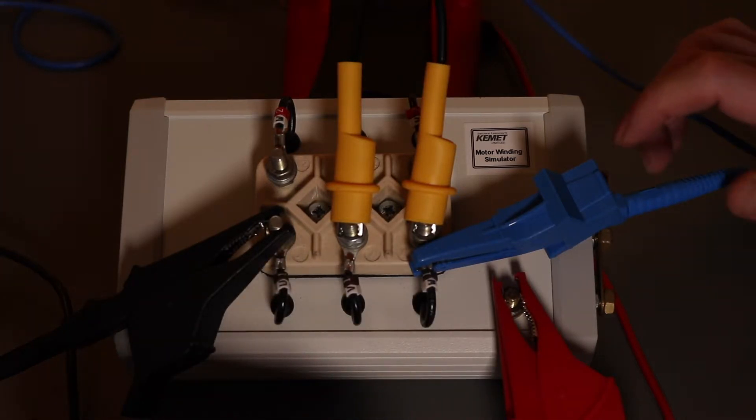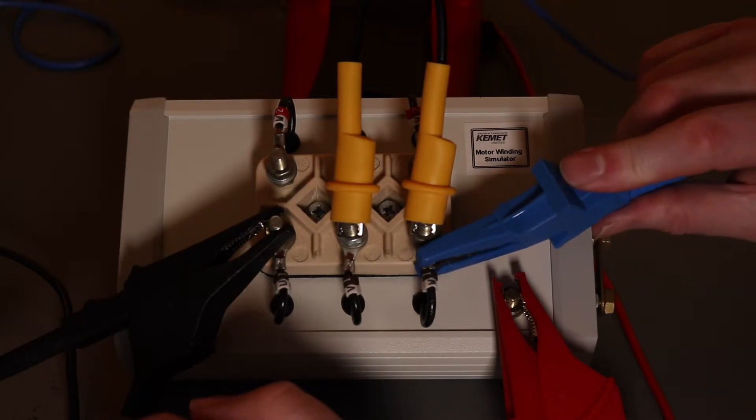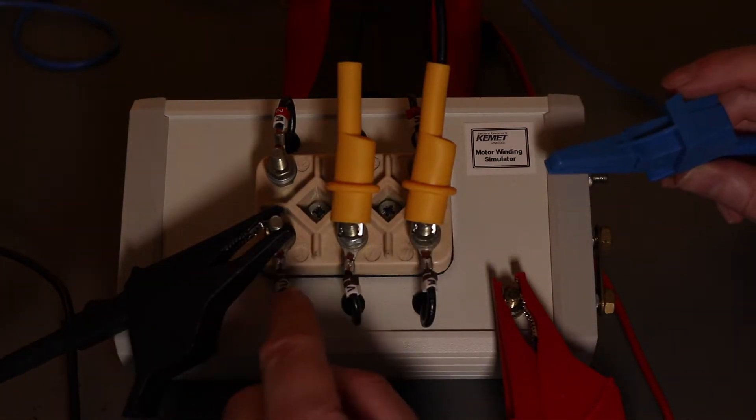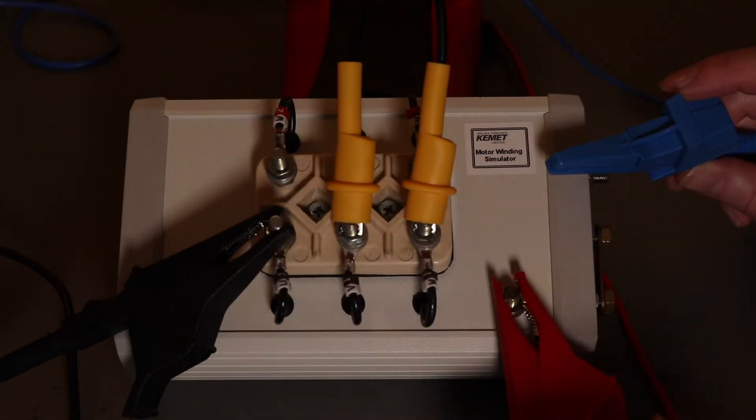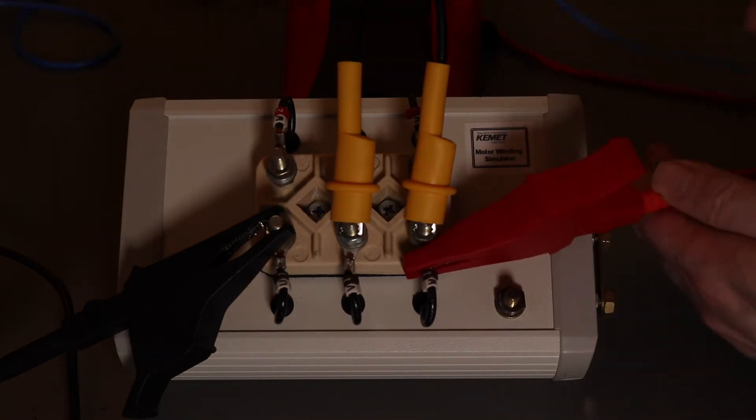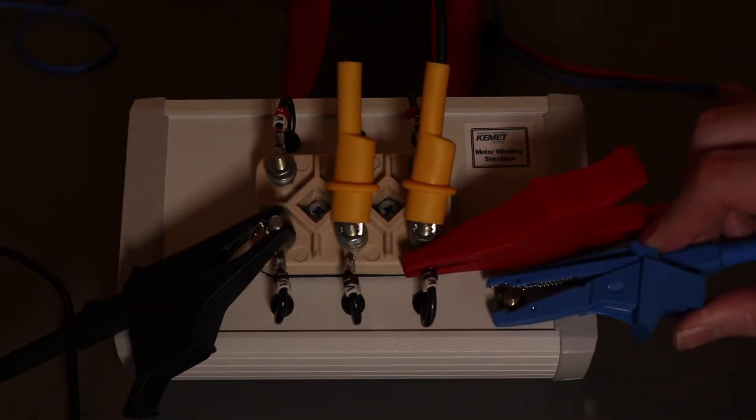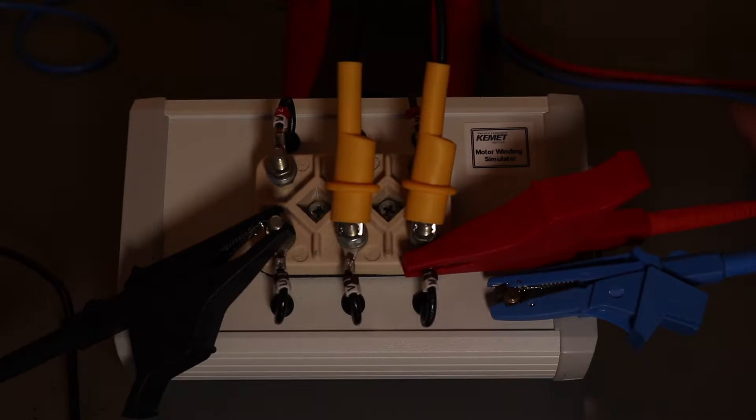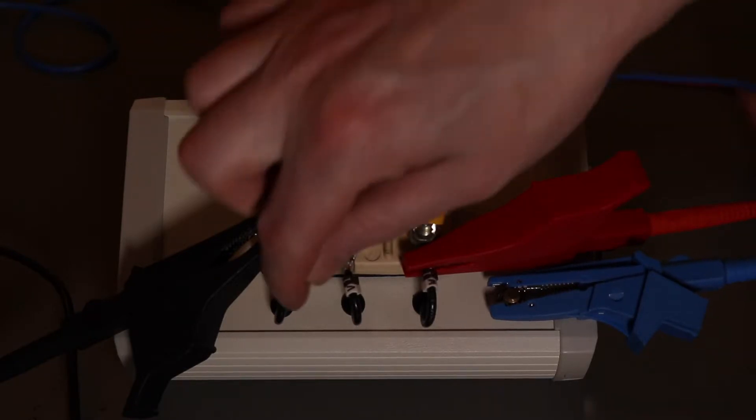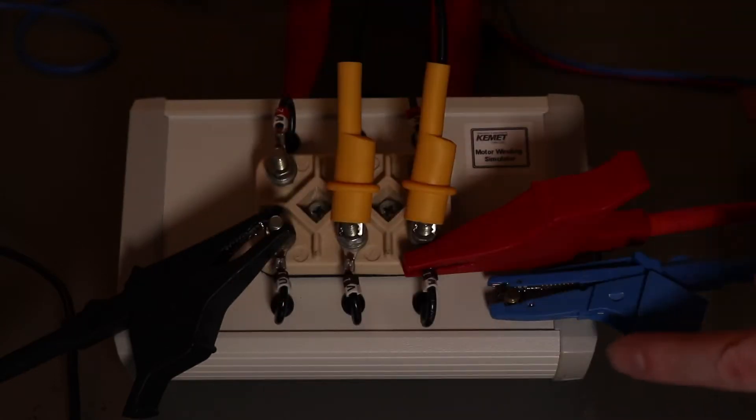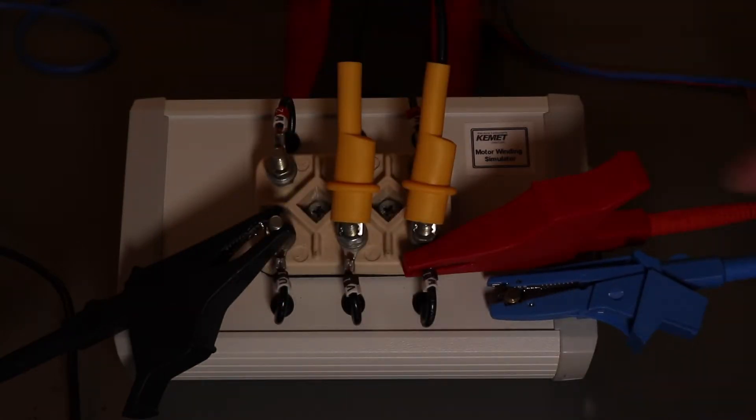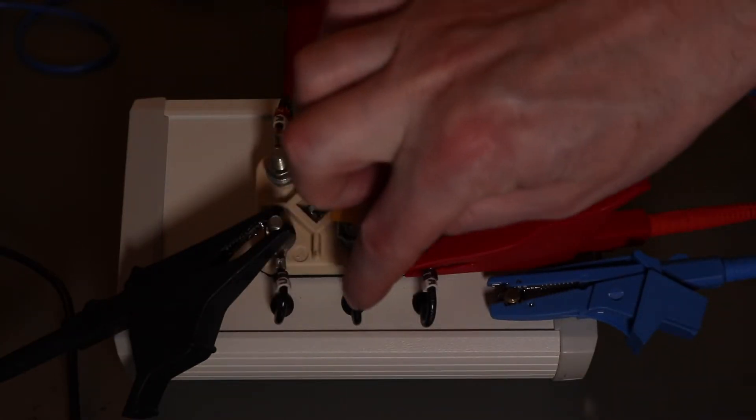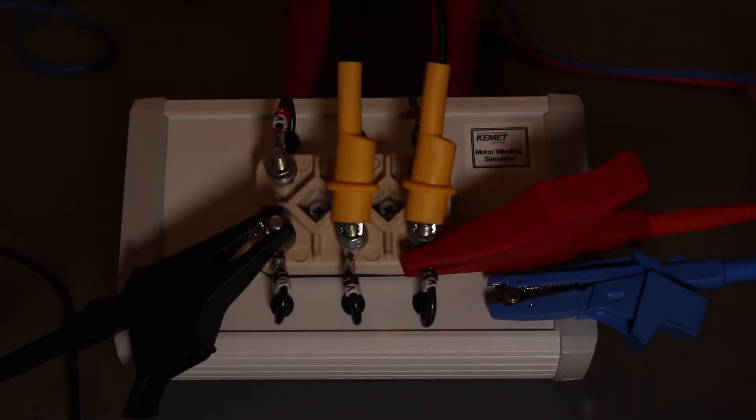I can reverse that. If I wanted to get a leakage reading of this phase into the other two phases, I can do the insulation test off of there and clip the guard terminal onto the chassis earth. Then any reading from this phase that goes down to the chassis is taken from the result and I just get the reading of this phase into either of these two phases.